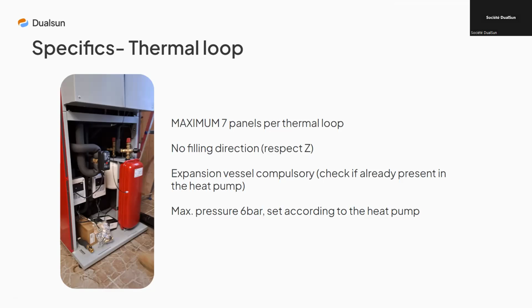There is no filling direction. You need to respect the Z, which means if I enter at the bottom right, I exit at the top left, and vice versa. Then a solar expansion vessel is mandatory. Check if one is already present in the heat pump, it's possible, which also has its own expansion vessel for the heating circuits. And finally, the maximum pressure, as we already see, is 6 bar, and this pressure is adjustable according to the heat pump, which is generally around 1 or 2 bars.